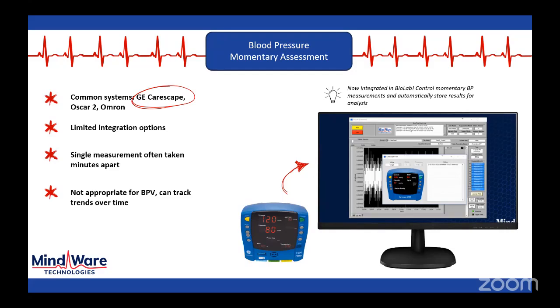The other cool thing about software controlled setup, as opposed to just pressing the buttons on the instrument, is we can schedule things and we can cycle things in more complex ways. So within BioLab, we're able to tell the device, I want to take a measurement every so many minutes, and I want this to repeat 10 times. And so you can, per the needs of your protocol, adjust that and then ensure that this is automatically happening. You don't have to press a button, you don't have to think about it. It just takes the measurements, stores it back in BioLab, and you're good to go from that point forward.